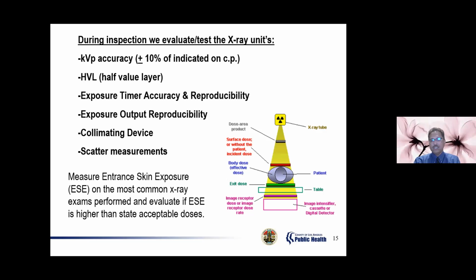Well, what you're seeing is the light sometimes, but that light doesn't mean anything. That light you see on the table sometimes doesn't coincide with what you see up here on the collimating device. That triangle might be kind of wider on the bottom, only because the blades on the collimator are not adjusted, it's out of whack. So we want to make sure that collimating device is within limits.